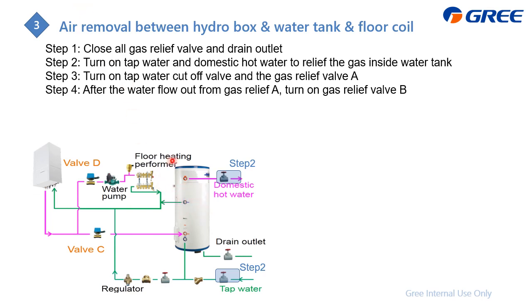And after that, step 3 is to turn on this cut off valve and also the gas release valve A. These two release the air of the circulation. And after we confirm there is water flowing out from the gas release valve A, which comes out from here, then we can turn on this one to also release the air.